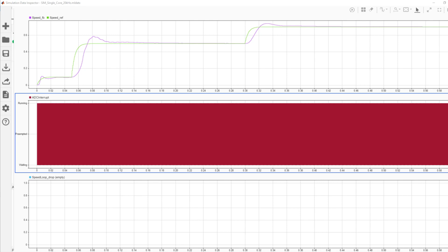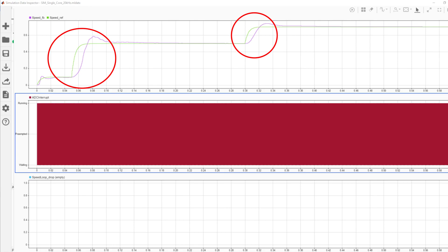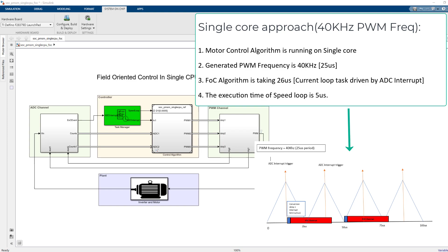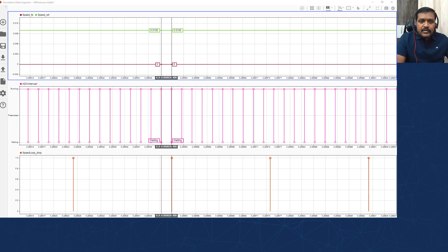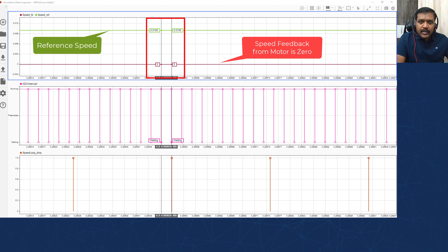Now we can see that with 20 kilohertz, everything works fine as expected without a task overrun, and the motor speed is tracking the reference speed. Now let's revise the PWM frequency to 40 kilohertz and run the simulation again. Now the speed feedback from the motor is 0, where it is expected to follow the reference speed highlighted in green color. This is because the current loop task is overrunning, leading to the drop of the speed loop task as shown in the graph on the bottom. Because with 40 kilohertz PWM frequency, the current loop task is expected to finish its execution within 25 microseconds, but it is taking 26 microseconds.